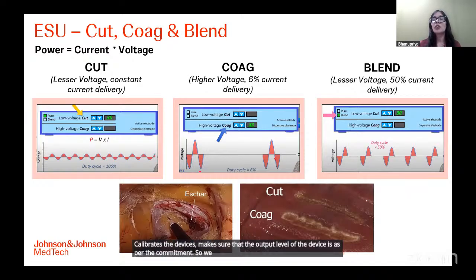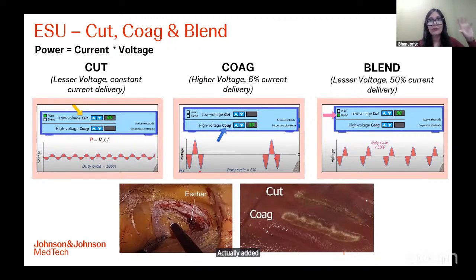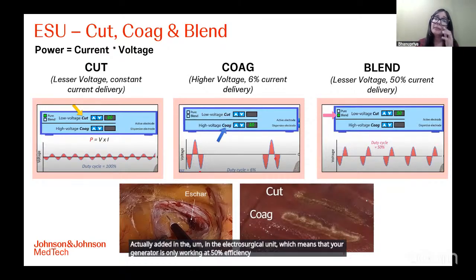So we have a term called the output level, which is the power efficiency ratio of an equipment. For example, the input power is 100, but the output power is only 50, which means the current flowing in the patient body is only 50% of what you have actually set on the electrosurgical unit, which means that your generator is only working at 50% efficiency. That is something that you do not want, which is where preventive maintenance and calibration of the devices is very important.